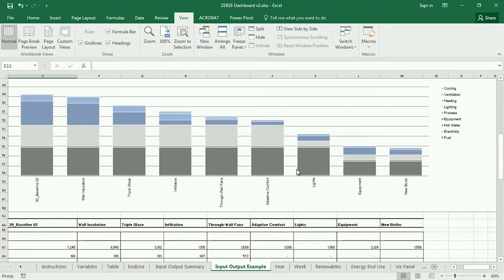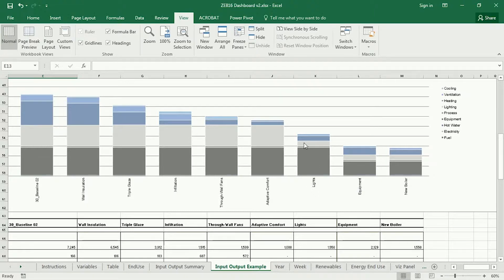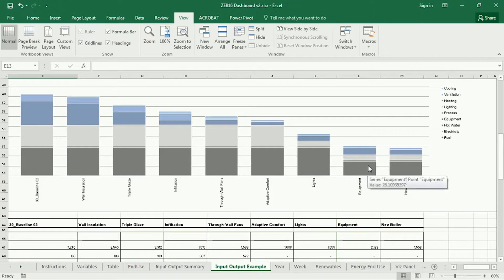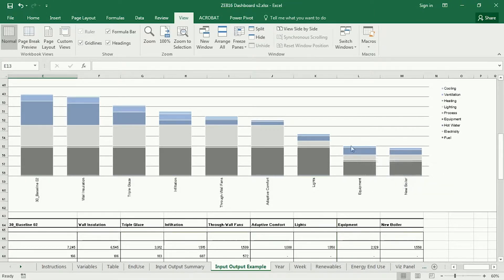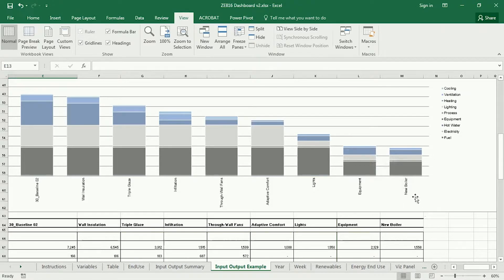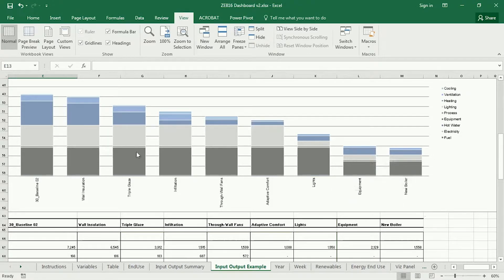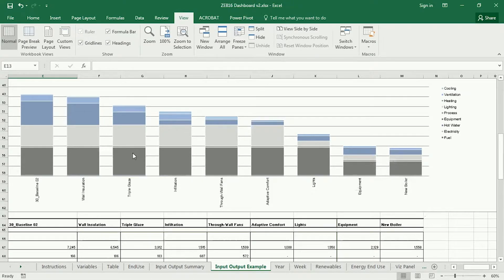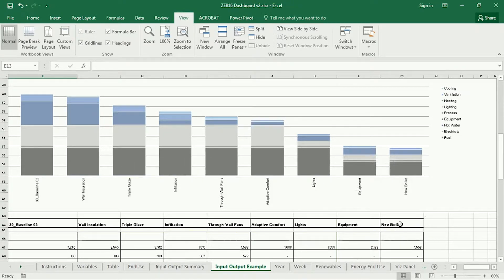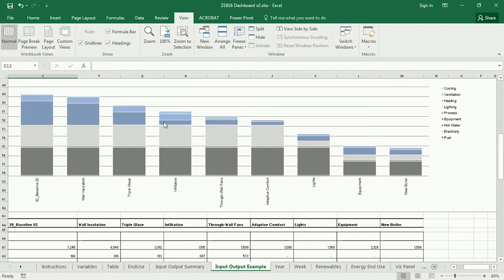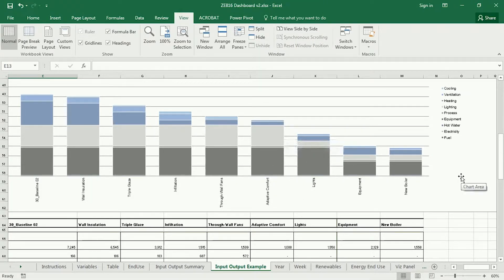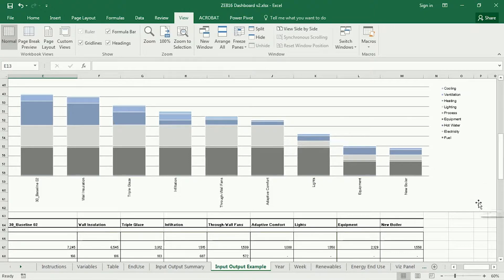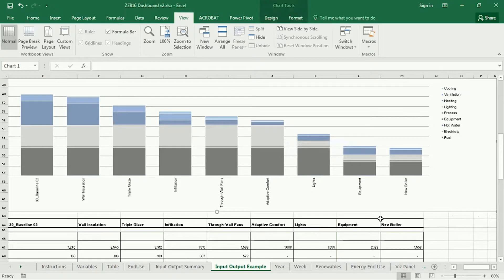And actually, you should see also down at this end, as I reduce the lights and the equipment, you also see some pretty dramatic changes that will also then impact the heating and cooling again. Now, one thing that is true is that when you have the heating, cooling, process loads, equipment, hot water, ventilation, everything in this graph, it sometimes can be difficult to see what changes are responsible for what. This is one method of visualizing the data, but you can also copy this graph.